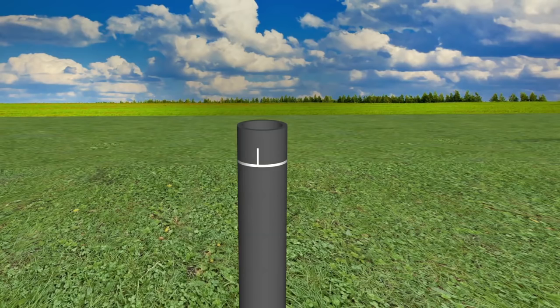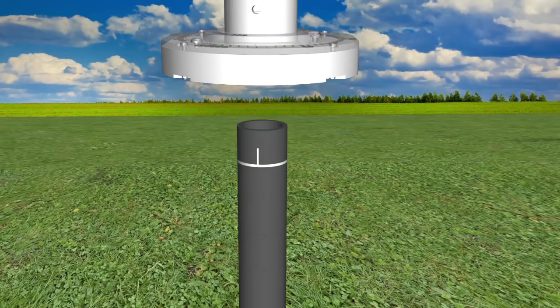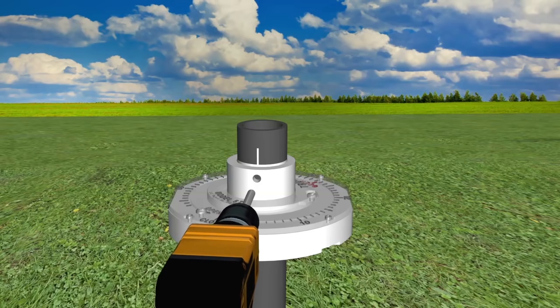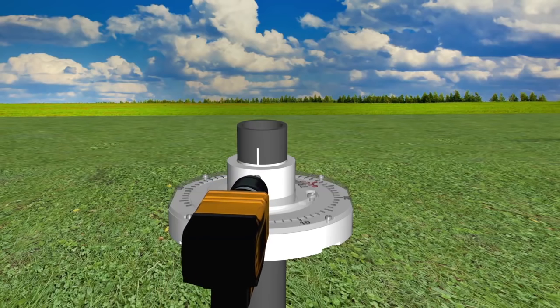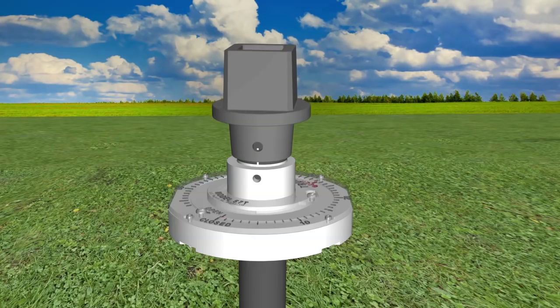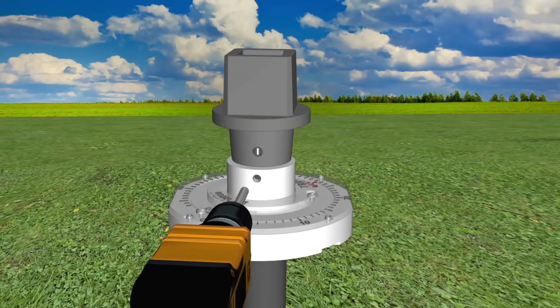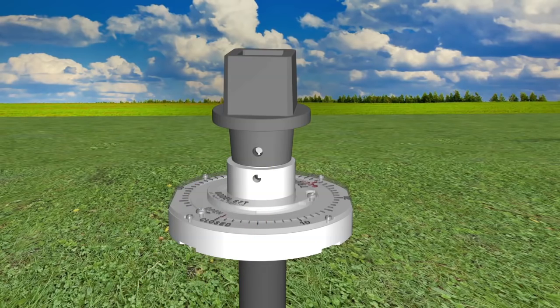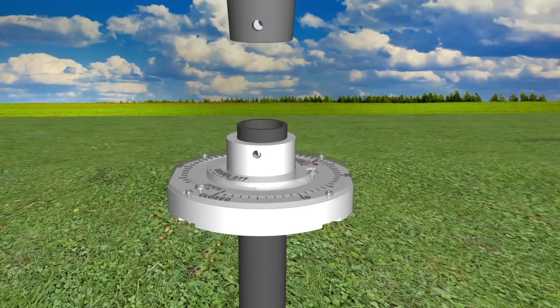Slide the position indicator on the extension stem and align the end of the drive hub and pilot hole with the drill and pin mark. Using the pilot hole in the position indicator drive hub, drill through the extension stem and position indicator drive hub to accept a 5 16th inch removable pin. Next, place the 2 inch operating nut on the extension stem and using the pilot hole, drill through the stem to accept a 5 16th inch removable pin.